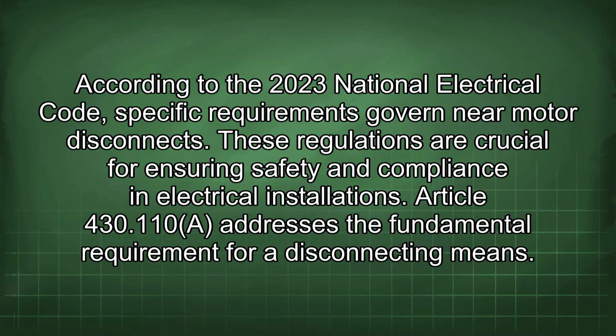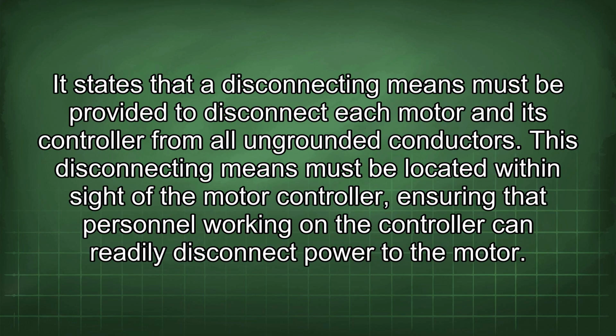According to the 2023 National Electrical Code, specific requirements govern near motor disconnects. These regulations are crucial for ensuring safety and compliance in electrical installations. Article 430.110 addresses the fundamental requirement for a disconnecting means. It states that a disconnecting means must be provided to disconnect each motor and its controller from all ungrounded conductors.